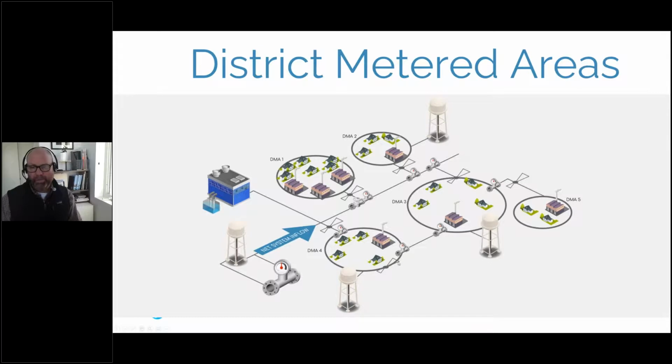You do have to have the right sensor placement, and you have to have the right zonal connections, physical pipe connections. But the idea of a DMA is that you account for all your inputs, your storage ins and outs, and all your outputs, so that you can very accurately do a water balance at a smaller level within a sub area of your system.